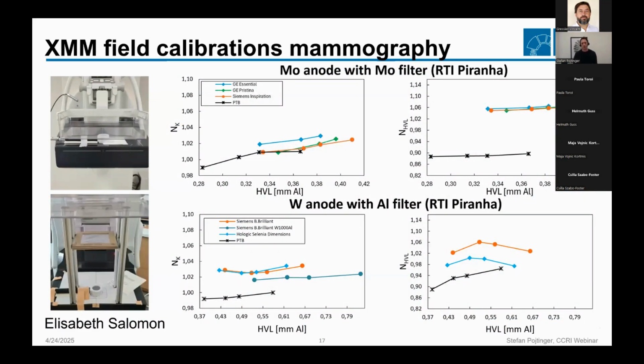An additional uncertainty or additional challenge arises if you're going to clinical beams. In this experiment we did at PTB, we compared calibration factors for XMMs that we determined at our calibration lab with calibration factors we determined at clinical beams. What we did is we used all of the current models of the XMMs of all manufacturers, and we determined calibration factors in our laboratory. And that's what you can see here in black. Then in addition to that, for the same anode filter combination, we calibrated a good secondary standard ionization chamber, the RC6M ionization chamber. And then we moved with the XMMs and our secondary standard to clinics, to real clinical machines. And there we also determined the calibration factors of the XMMs.